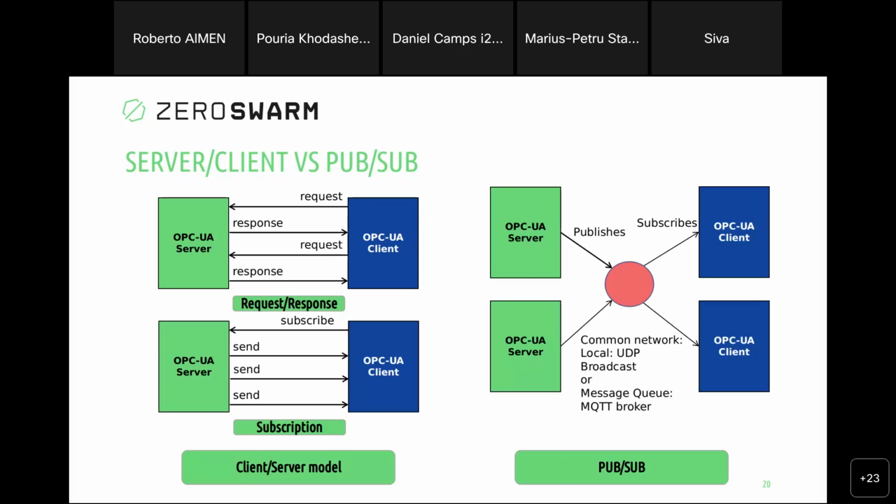When you created all this node set, you need to correlate that with your firmware. When you are using a client which stays on a computer somewhere or on your mobile phone and it interrogates an OPC UA server lying on a device in the field, a PLC, a modem, a drive, a sensor, you need that OPC UA server to connect to the firmware and really retrieve the real information which exists there.